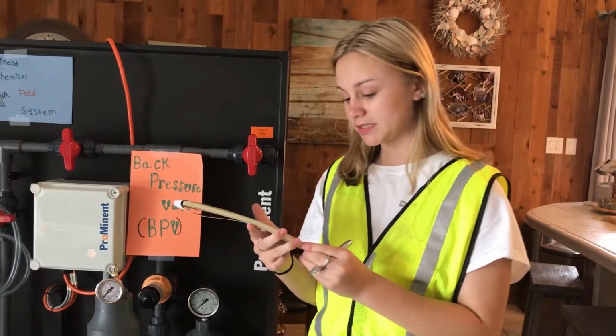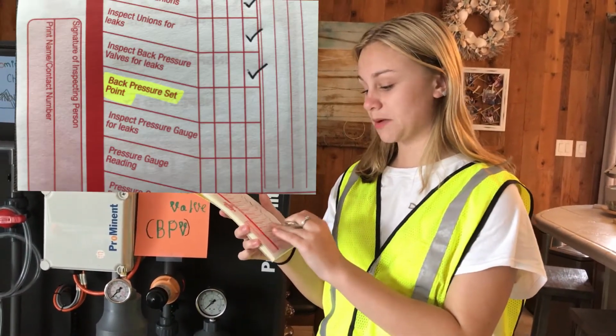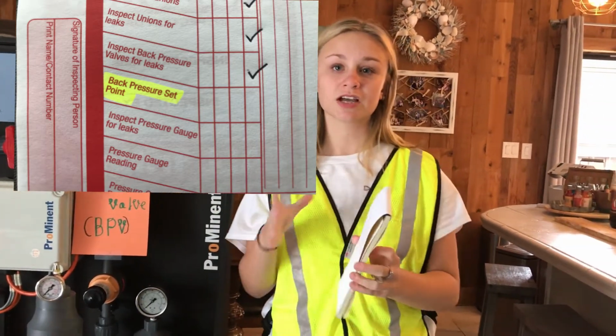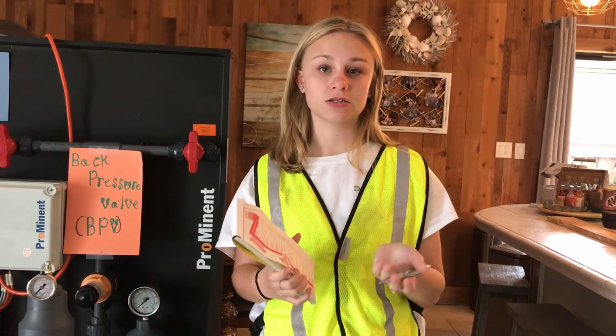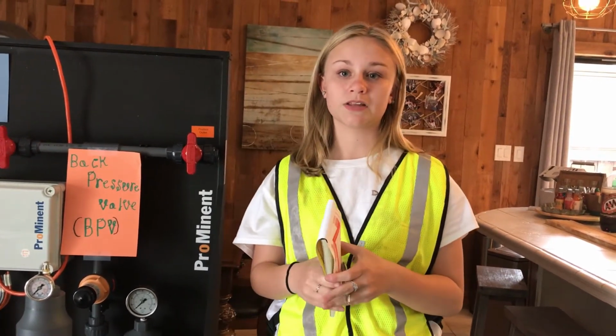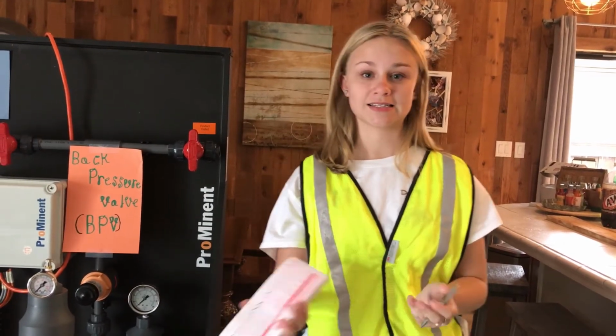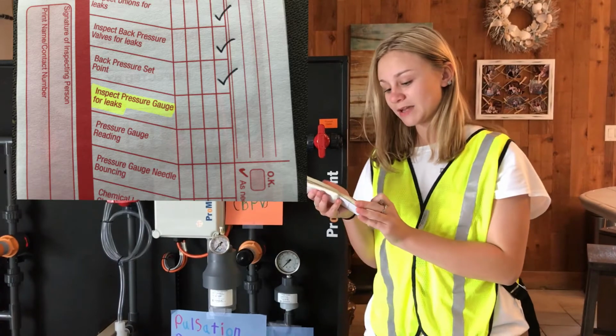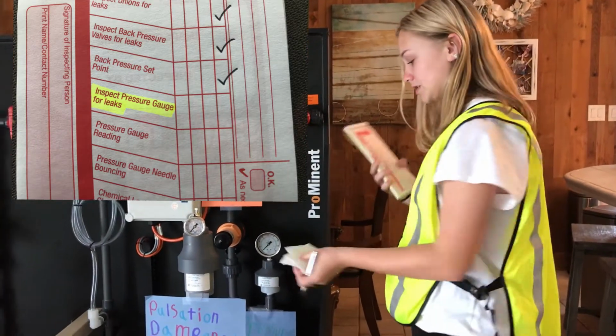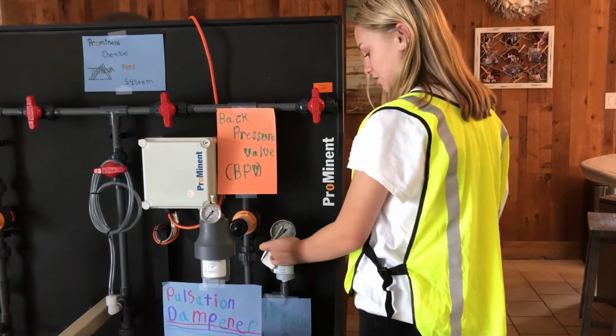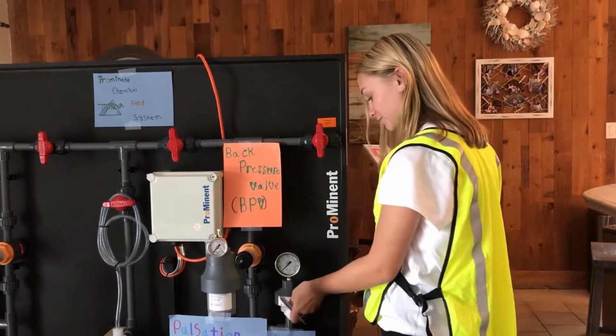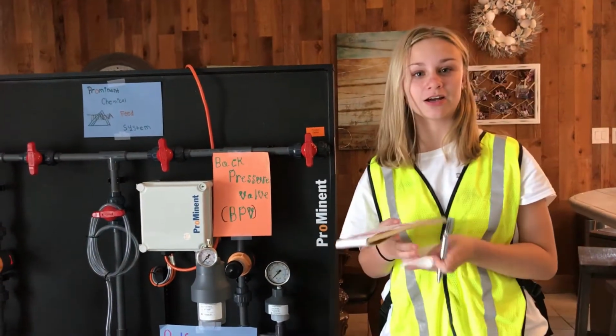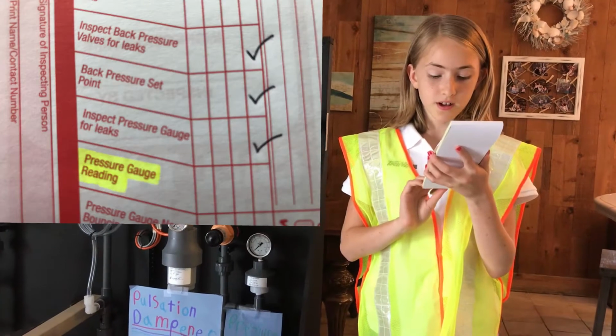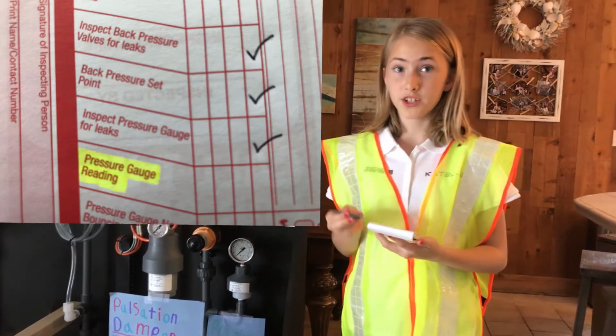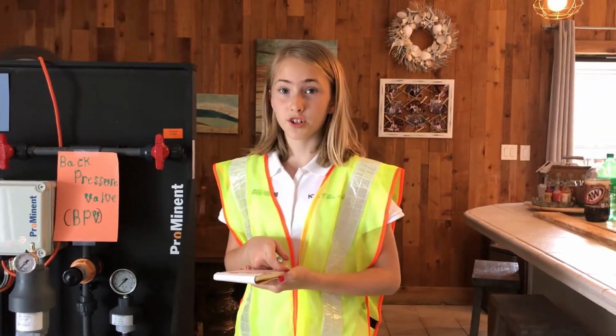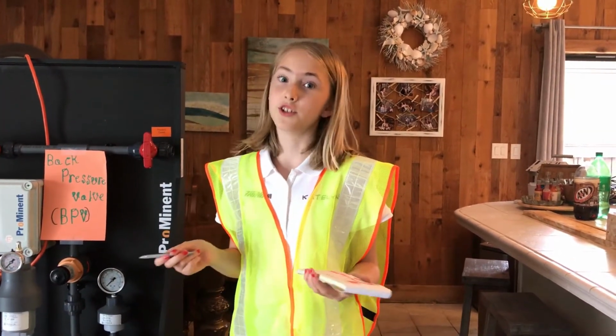Number 13 on the list in the booklet is back pressure set point. While the skid is operating, check the pressure gauge and note what it is reading. If it is not reading properly, the gauge is broken or the back pressure is not set. Step 14 in the booklet is to inspect pressure gauge for leaks. Typically, it leaks around the threaded areas. So you will check that for any crystallization or moisture in it, and that's how you'll check if there's a leak or not. Step 15 on your booklet is pressure gauge reading. While the skid is operating, check the pressure gauge and note what pressure it is reading. If it is not reading properly, the gauge is broken.